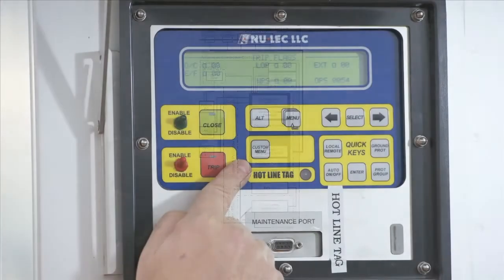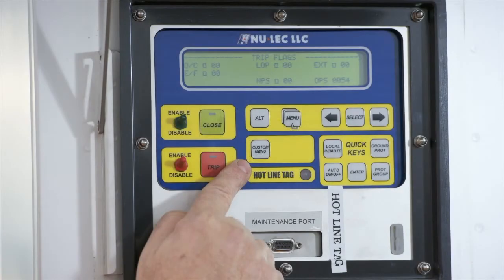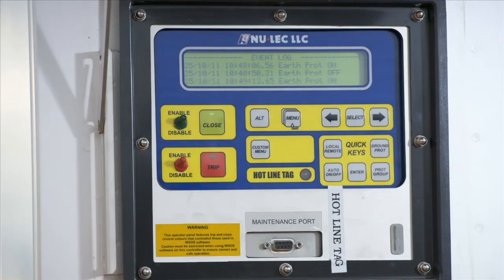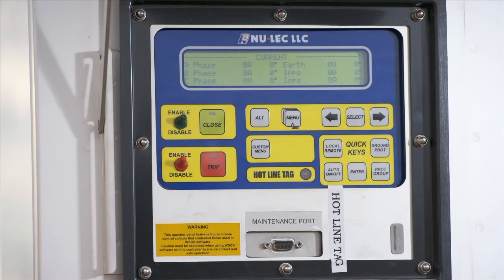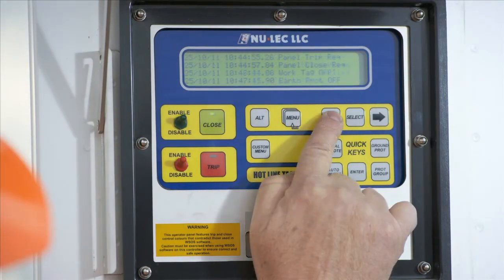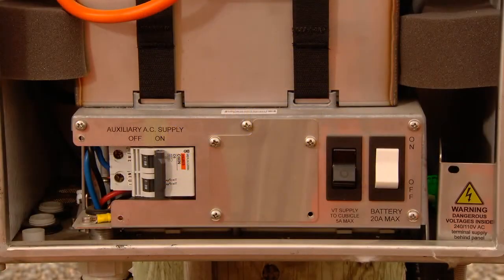The controller electronics incorporate the functions of an overcurrent and earth or ground fault protection relay, an auto reclose relay, and a remote terminal unit. Additionally, the electronics can measure line current, voltage, real and reactive power, fault currents, and harmonics, and perform waveform capture. These data are stored for transmission or offline analysis. The ADVC contains a built-in microprocessor-controlled power supply that provides uninterrupted operation of not only the switchgear and protection relay, but also the communications radio or modem.